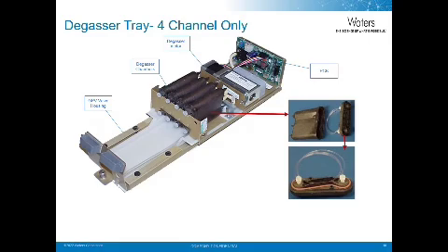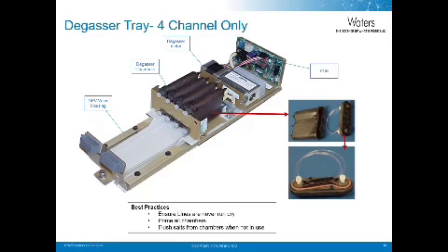The degasser PCB controls the vacuum, and you can check the board by removing the hose from the PCB and testing the vacuum itself. Chambers should not be taken apart since you probably won't be able to get the vacuum seal back. Remember, all these chambers are connected, so if one has an internal leak after a period of time, they will all have solvent in them. The current style degasser has 4 channels, and the degasser on the 2795 Alliance system has 5 channels. As far as best practices to ensure the life of your degasser, ensure lines are never run dry. Make sure to prime all chambers and flush salts from chambers when not in use.